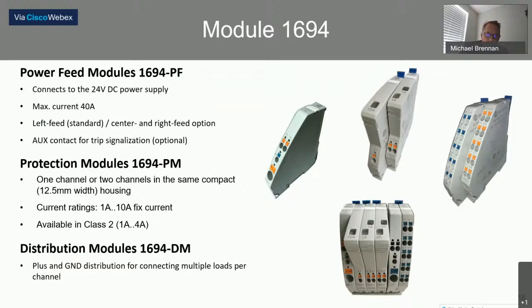The protection modules, those are available in different current ratings between 1 and 10 amps, and you can have either one circuit or two circuits for each of the same housing. So if we were looking at, again, our previous application where we had 11 circuits, I could have one power feed module, I could have 6, call it 4 amp each outputs, and then have my common as well.